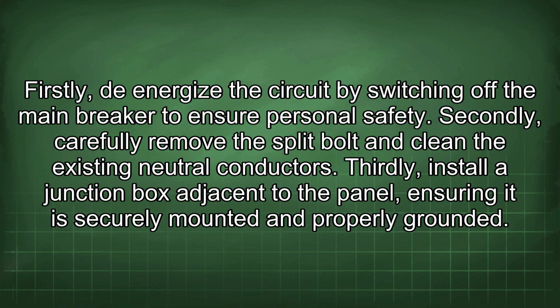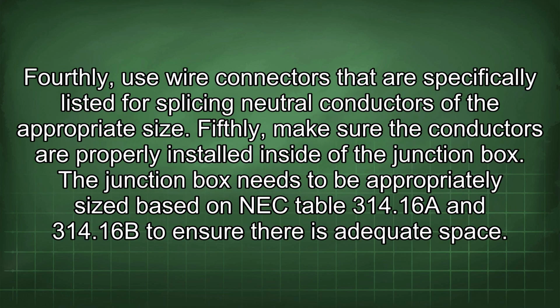Thirdly, install a junction box adjacent to the panel, ensuring it is securely mounted and properly grounded. Fourthly, use wire connectors that are specifically listed for splicing neutral conductors of the appropriate size. Fifthly, make sure the conductors are properly installed inside of the junction box. The junction box needs to be appropriately sized based on NEC Table 314.16(A) and 314.16(B) to ensure there is adequate space.